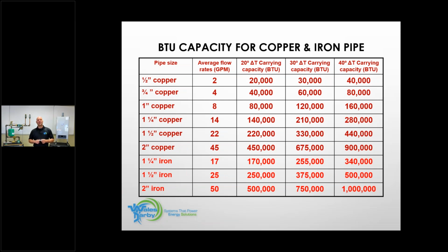You can't always go by the pipe diameter that the manufacturer has exiting their product. Most cast iron manufacturers go to the largest diameter size because those sections are used across their whole run of boilers and BTU range. Most manufacturers on the condensing side will have a smaller diameter pipe coming out of the bottom to carry the BTU load, and you are expected to increase that pipe. The reason it's smaller is because inside of this box, there's not a lot of room for large diameter piping, so they will normally calculate the piping into the head loss of the heat exchanger, and then when you exit the boiler, whether it's top, bottom, or side, you are expected to increase the size of the piping in order to support the BTU that boiler will produce.